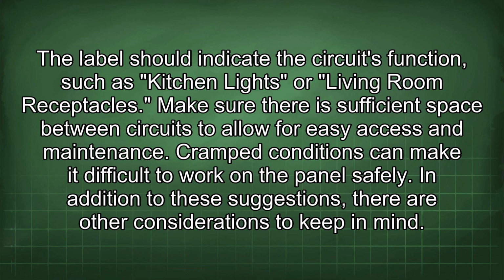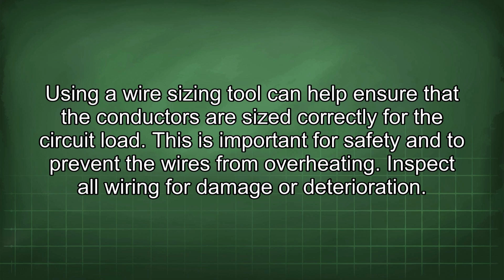Make sure there is sufficient space between circuits to allow for easy access and maintenance. Cramped conditions can make it difficult to work on the panel safely. In addition to these suggestions, there are other considerations to keep in mind. Using a wire sizing tool can help ensure that the conductors are sized correctly for the circuit load. This is important for safety and to prevent the wires from overheating.